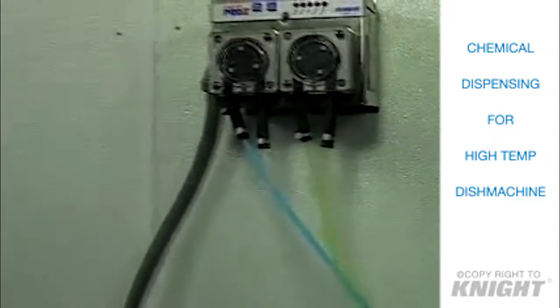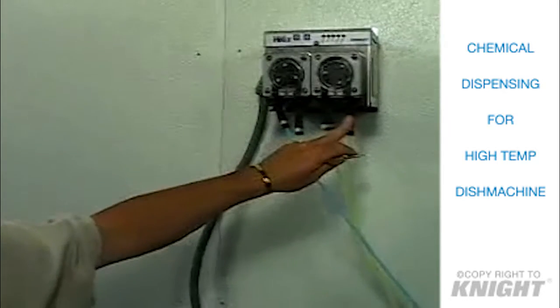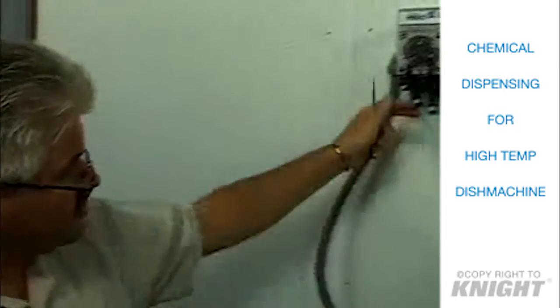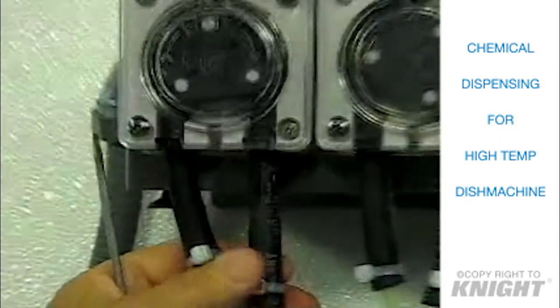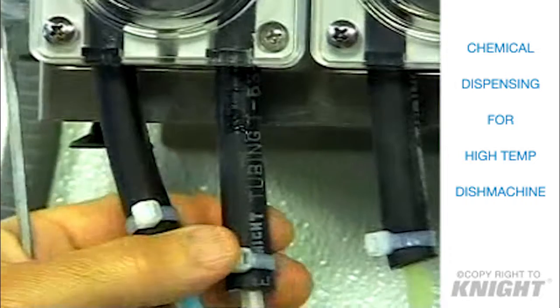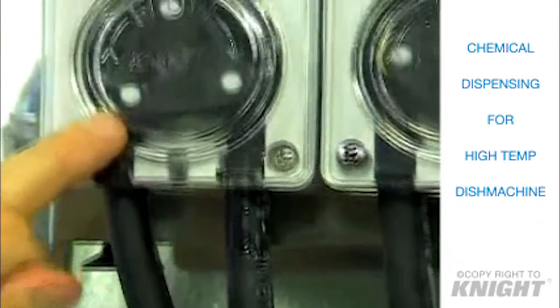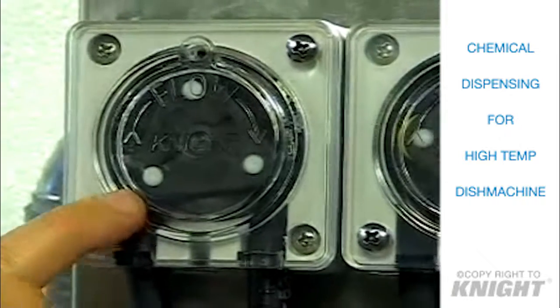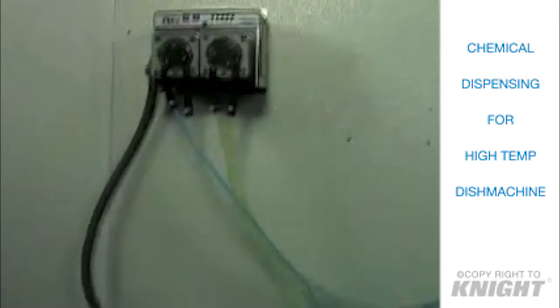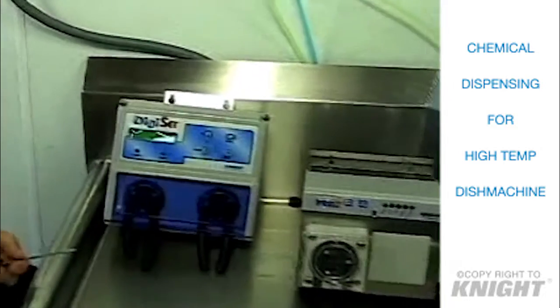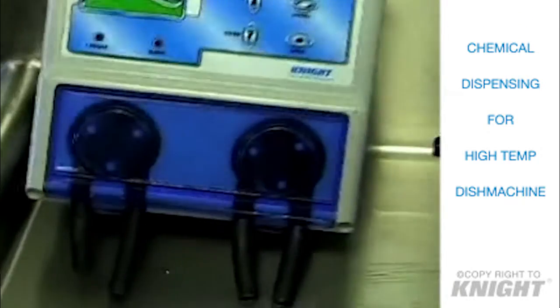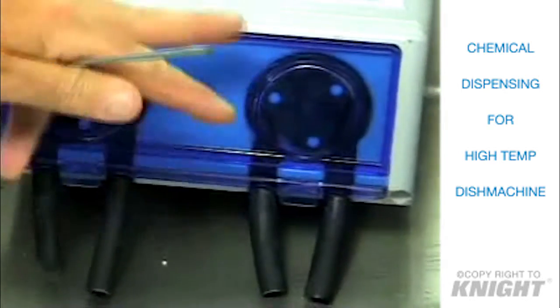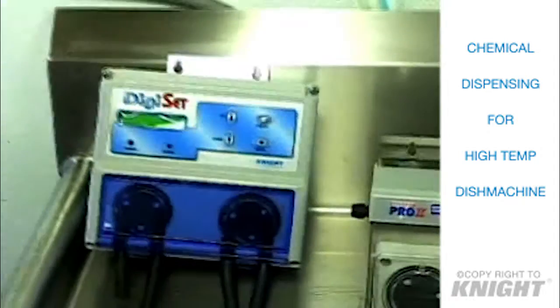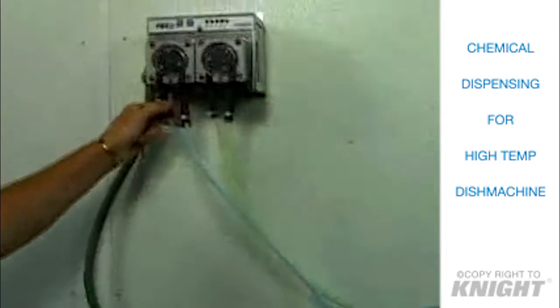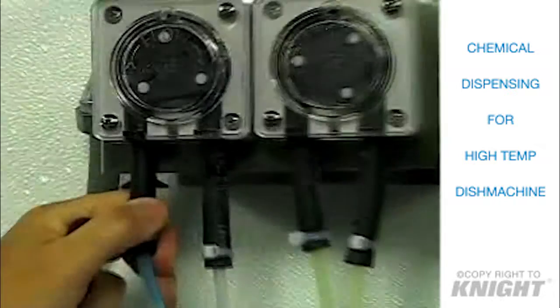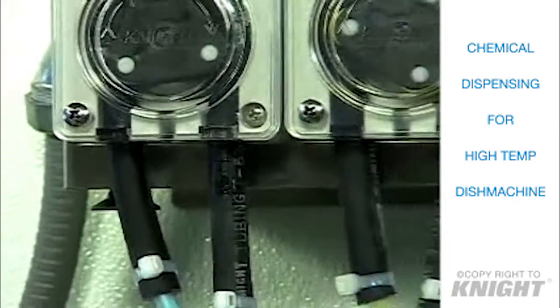It's very important that you match the roller with the right squeeze tube for proper pump longevity. On the squeeze tube for the rinse, it is a T53E squeeze tube, which is a 3/16 inch ID tube, and it works with the blue roller, which is called an RB553. All of our dispensers, the DigiSet and the MicroPro, when you're working with pumps on rinse, are always going to have a T53 and a blue roller, and if they're using a detergent pump, it's going to be a yellow roller with a T50. So it's important to know which one goes where, and it's also important that you have these available, because should that happen, you need to be able to react to your customers' needs right away.